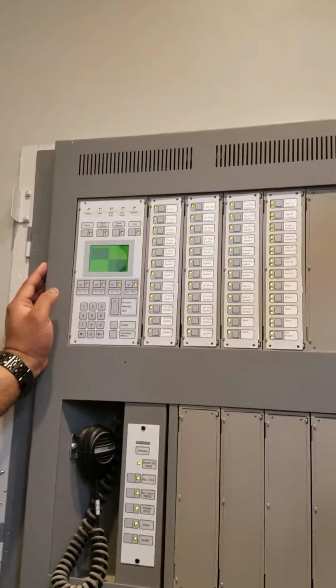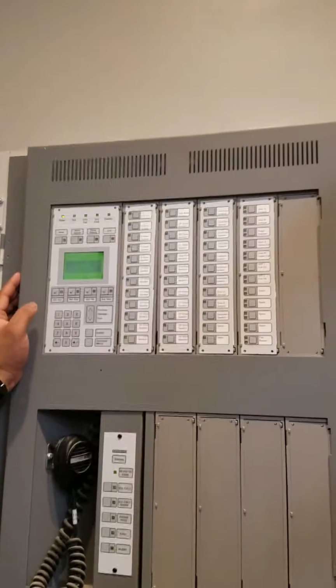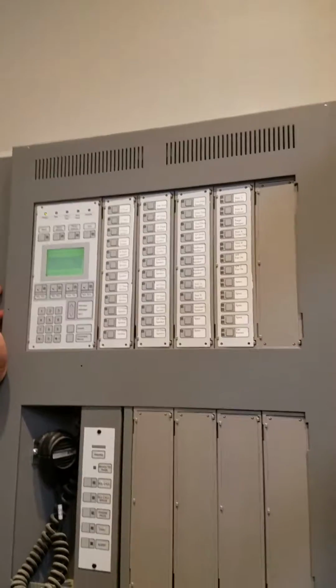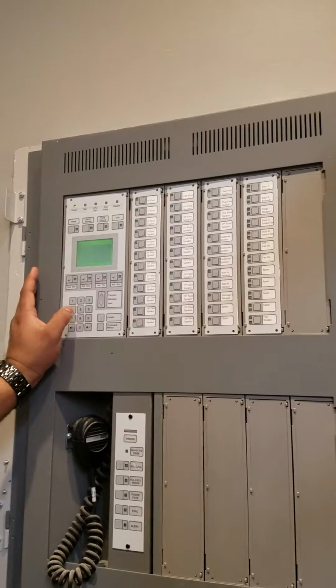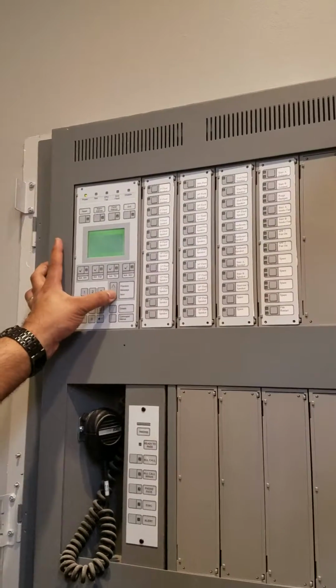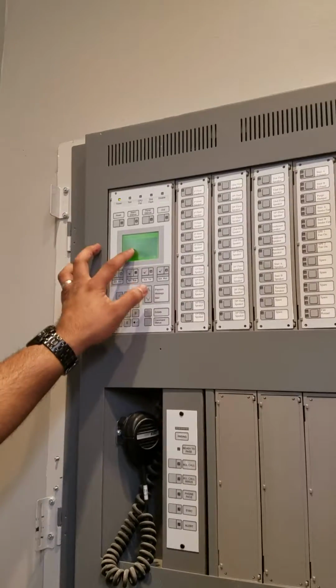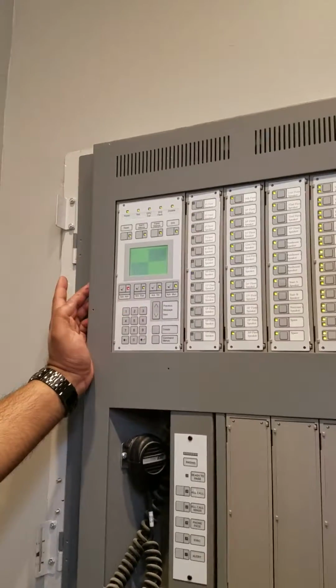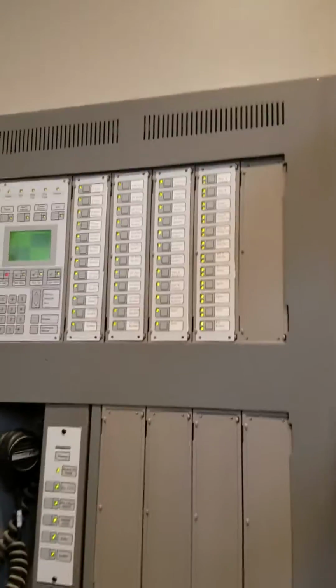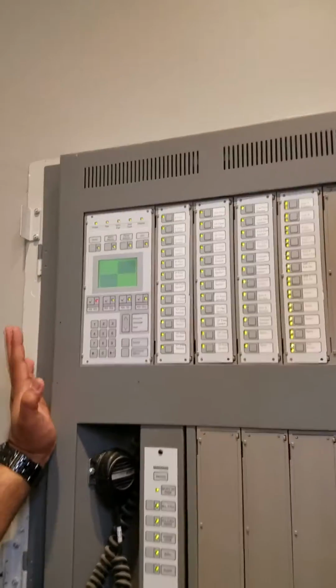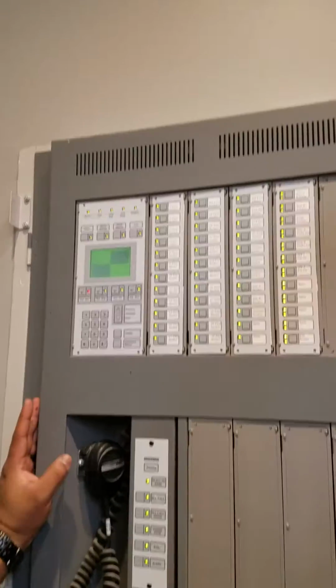You heard, Benji? I'll repeat it. And it would automatically clear on its own, right? So to do a lamp test, we will go to command menus. We'll scroll down to test, which is 8. And we want to do a lamp test, which is 3. So we'll hit 3, and it would automatically kick on for you. Okay. So that's a lamp test.